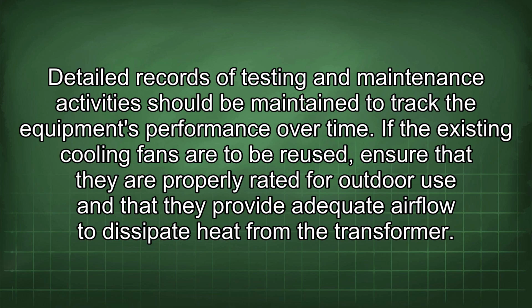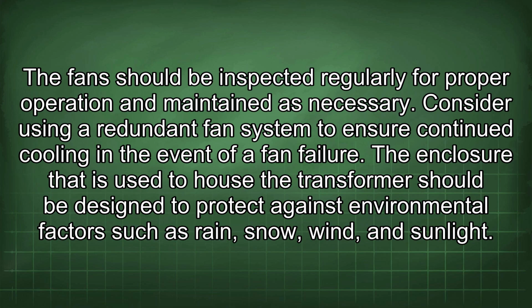If the existing cooling fans are to be reused, ensure that they are properly rated for outdoor use and that they provide adequate airflow to dissipate heat from the transformer. Fans should be inspected regularly for proper operation and maintained as necessary. Consider using a redundant fan system to ensure continued cooling in the event of a fan failure.